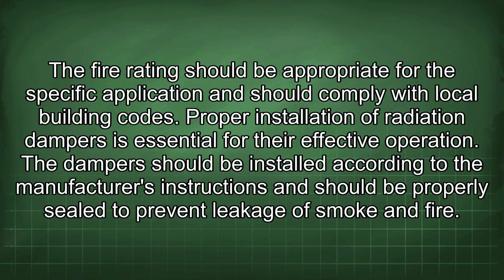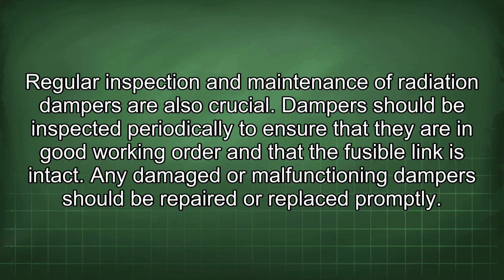Proper installation of radiation dampers is essential for their effective operation. The dampers should be installed according to the manufacturer's instructions and should be properly sealed to prevent leakage of smoke and fire. Regular inspection and maintenance of radiation dampers are also crucial. Dampers should be inspected periodically to ensure that they are in good working order and that the fusible link is intact. Any damaged or malfunctioning damper should be repaired or replaced promptly.